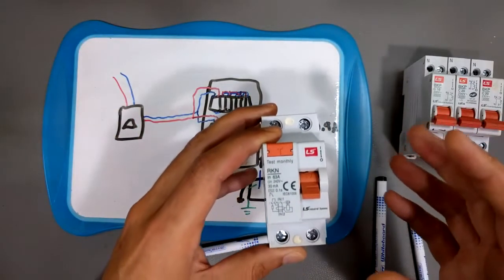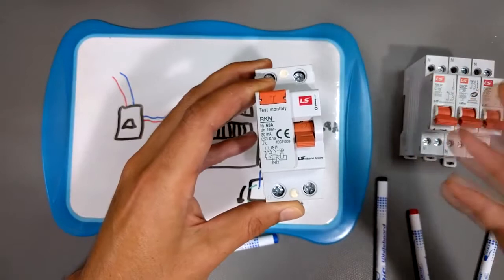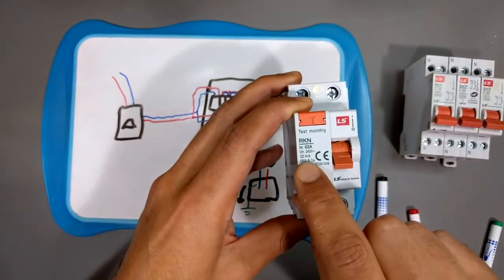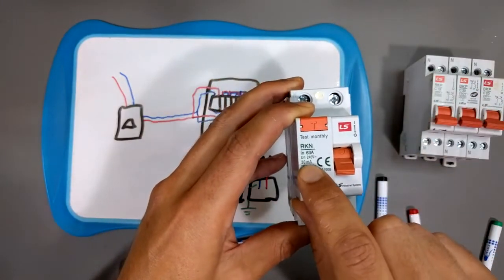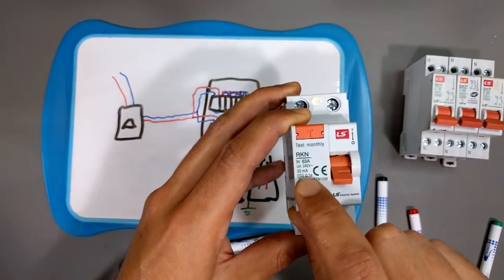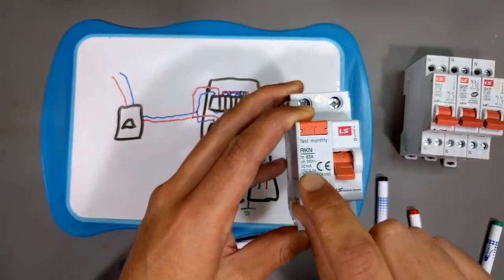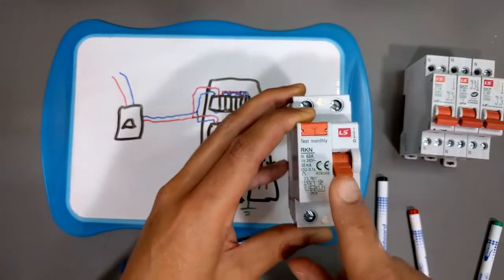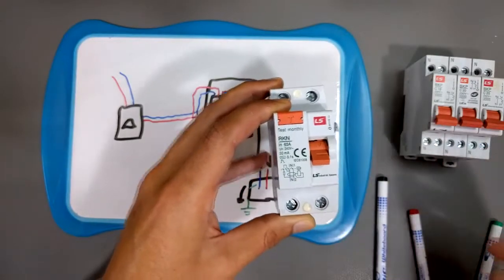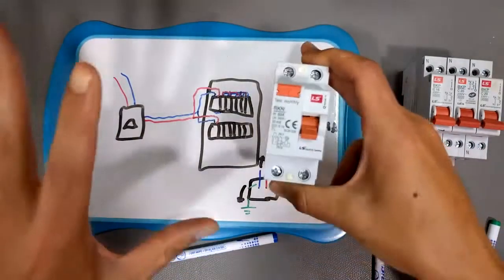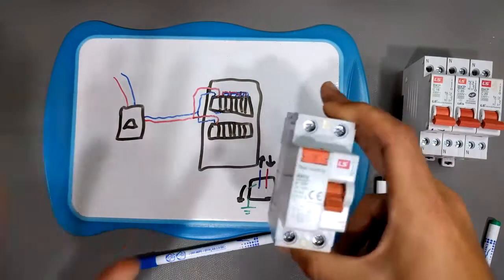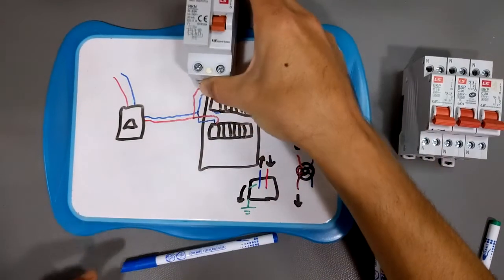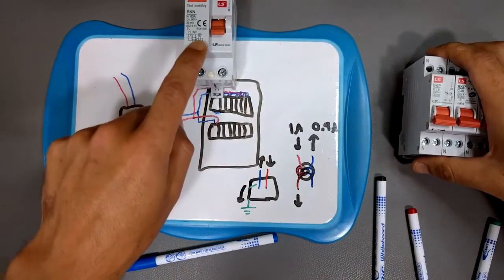The average person in average health, average age, if this guy trips at 30 mils, then you will not die. It will hurt like hell, but you won't die. That's the whole point. These are to protect primarily against electrocution. Okay, so that's a differential breaker / RCD / GFCI. And those are in our row here. As I said, each one of these protects a whole row of these guys.